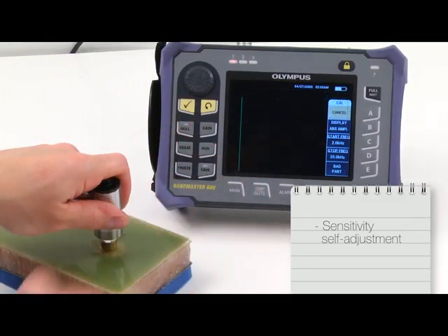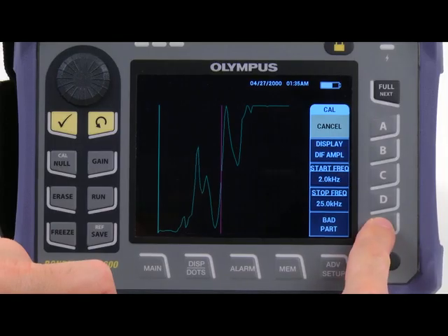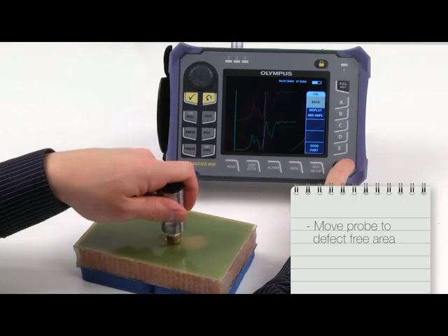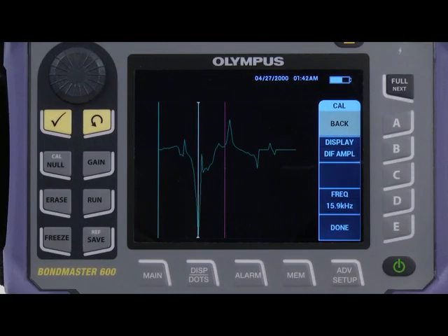While you hold the probe, the instrument will self-adjust its sensitivity. Once you feel the instrument has stabilized, press the BAD PART key. Move the probe onto a defect-free area, hold it there and press the GOOD PART key. Your result should resemble the following screen.